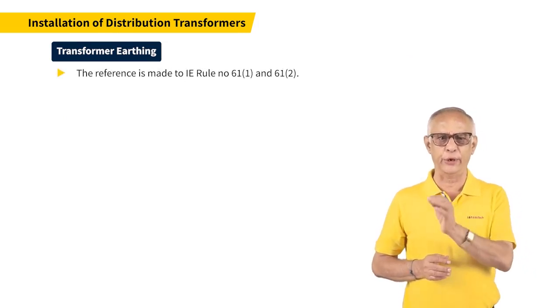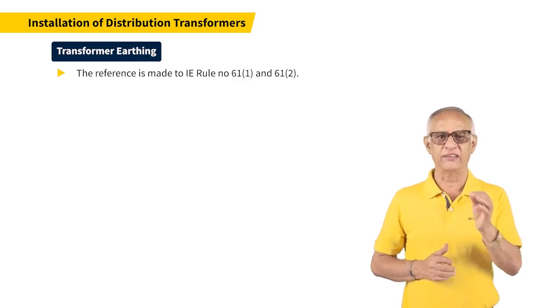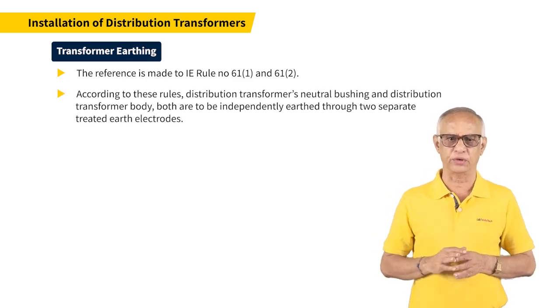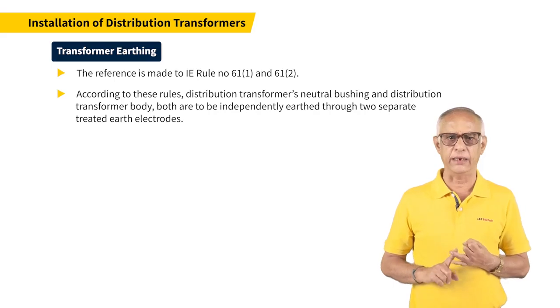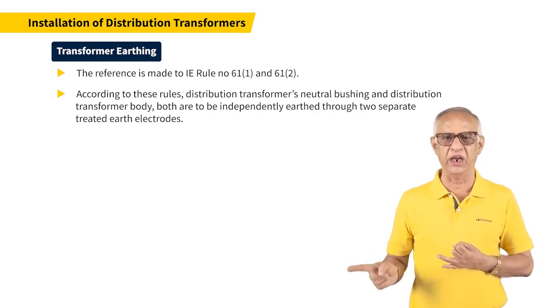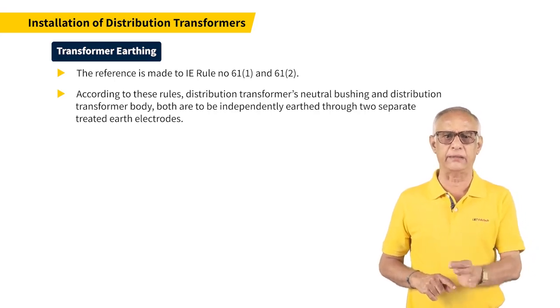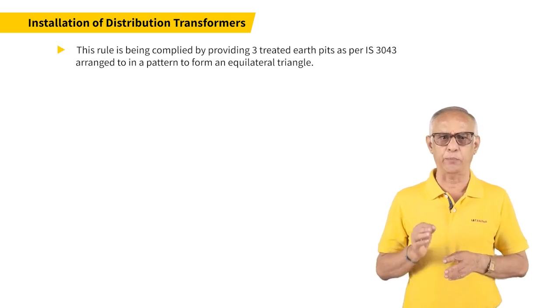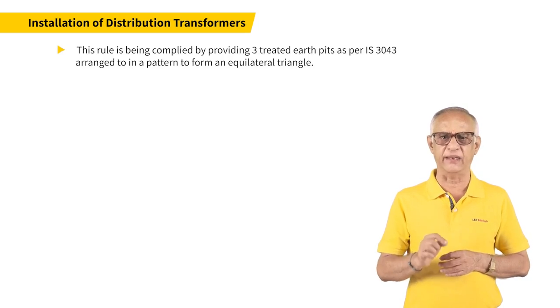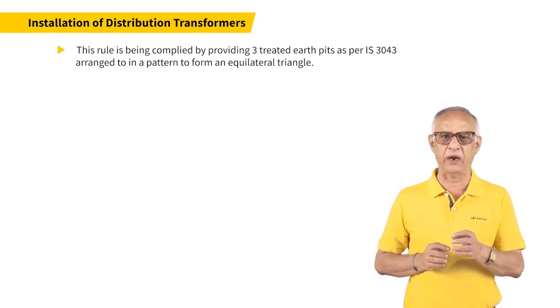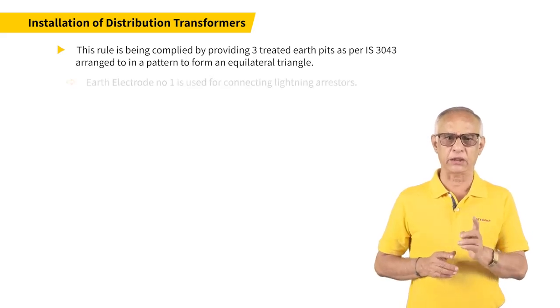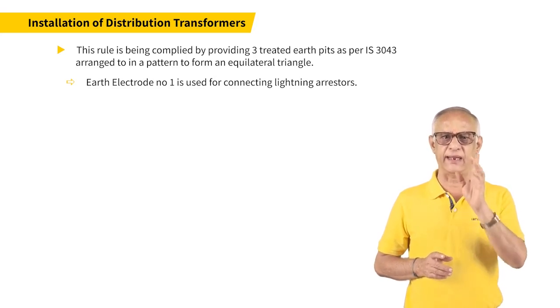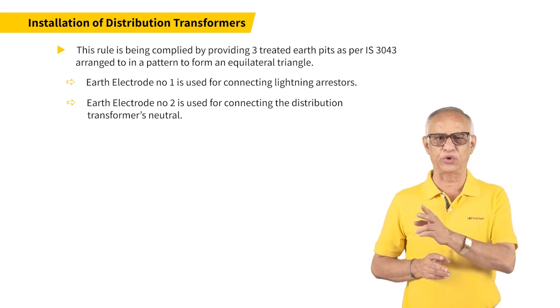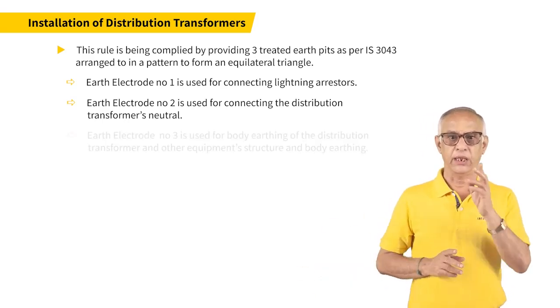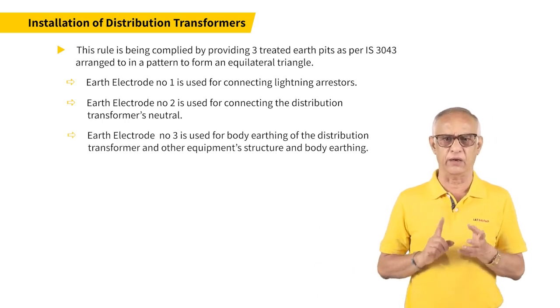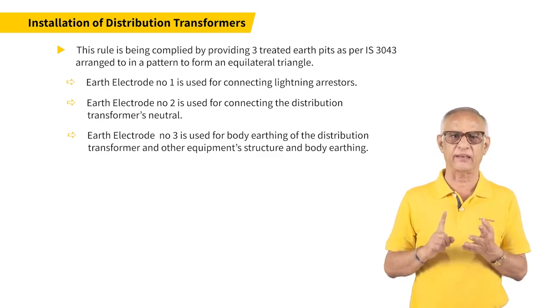The reference is made to IE Rule number 61 of subclass 1 and 61 of subclass 2. According to these rules, distribution transformer's neutral bushing and distribution transformer body both are to be independently earthed through two separate treated earth electrodes. This rule is being complied with by providing 3 treated earth pits as per IS 3043, arranged in a pattern to form an equilateral triangle. Earth electrode number 1 is used for connecting the lightning arresters. Earth electrode number 2 is used for connecting the distribution transformer's neutral. Earth electrode number 3 is used for body earthing of the distribution transformer and other equipment structures.